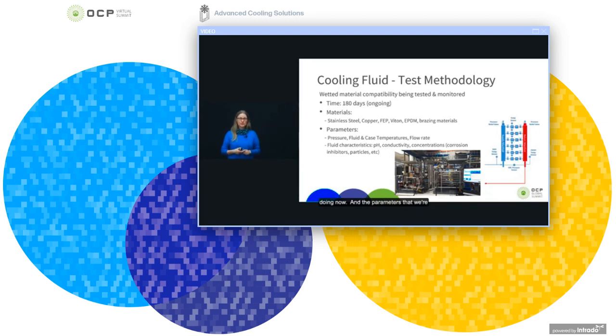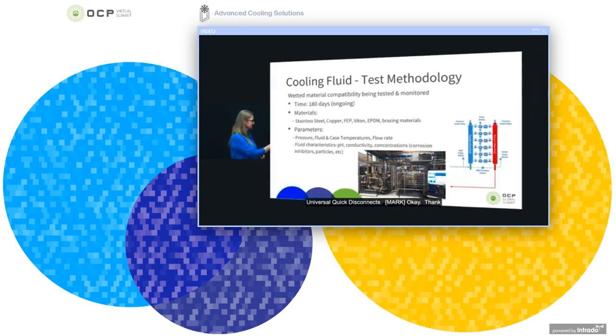And the parameters that we're tracking throughout the testing period are pressure, fluid and case temperature, and flow rates. For the fluid characteristics, it's pH level, conductivity, and then different concentrations in the liquid itself, for example corrosion inhibitors and particles that we're tracking as well. And with that, I'm going to hand over to Mark, who will talk about the universal quick disconnects.